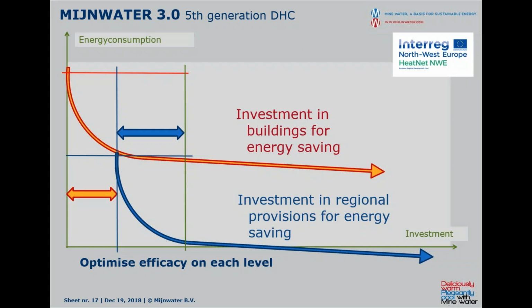What we are doing by looking at these dwellings is looking at the best, highest efficient investments on the building level, but combining those with the highest efficient measures on the district level. So if we have 2 buildings close together, one heating and one cooling, like a supermarket and dwellings, and we can serve 200 dwellings by one supermarket, there will be a very profitable investment in the district heating system to connect those 2 consumers.